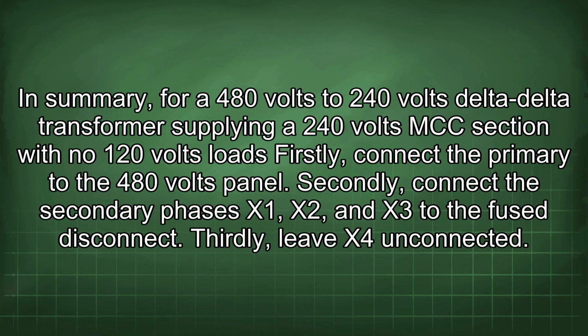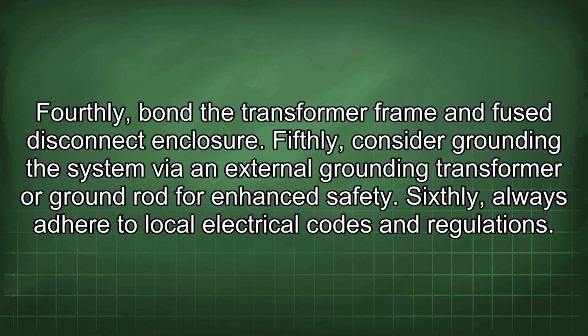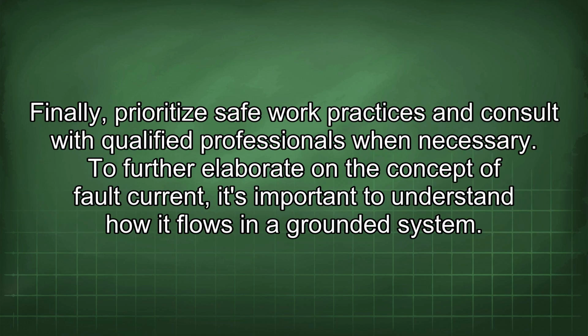In summary, for a 480 volts to 240 volts delta-delta transformer supplying a 240 volts MCC section with no 120 volts loads, firstly, connect the primary to the 480 volts panel. Secondly, connect the secondary phases X1, X2 and X3 to the fuse disconnect. Thirdly, leave X4 unconnected. Fourthly, bond the transformer frame and fuse disconnect enclosure. Fifthly, consider grounding the system via an external grounding transformer or ground rod for enhanced safety. Sixthly, always adhere to local electrical codes and regulations. Finally, prioritize safe work practices and consult with qualified professionals when necessary.